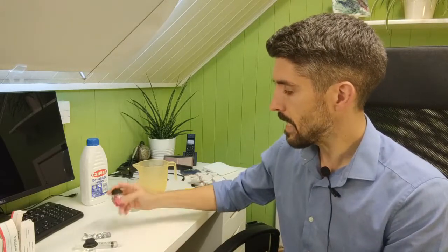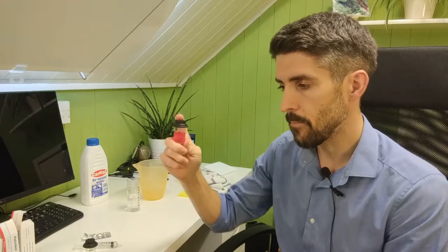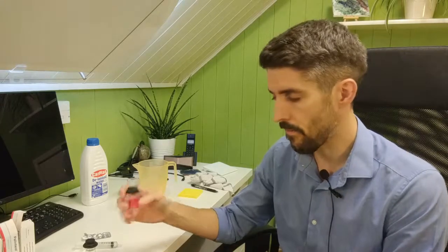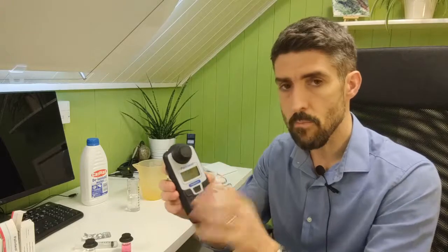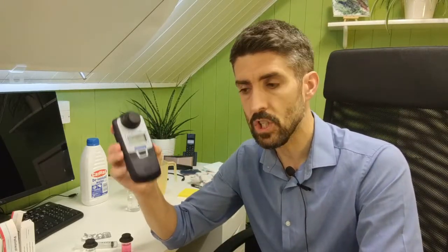What I will mention is if you do get a situation where there's so much chlorine that it's bleaching out the sample, or even if there's just a level of chlorine higher than 5, this photometer, and most photometers, aren't able to come back with an accurate reading. It will just say greater than 5. Or if it's bleached out, it will say 0. What you need to do in those situations is, first of all, do another test, because you might have a dud tablet or something like that. So always make that your common practice, that if you get a result that is a bit unusual, always do another test just to make sure that what you're getting is representative of the state of the water.